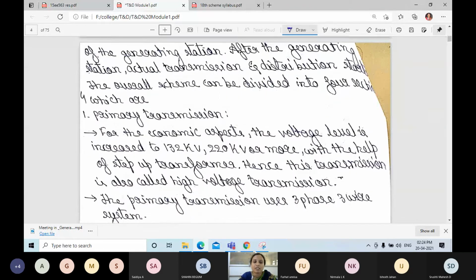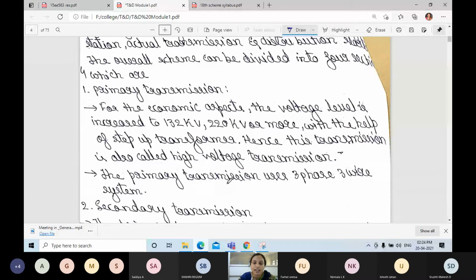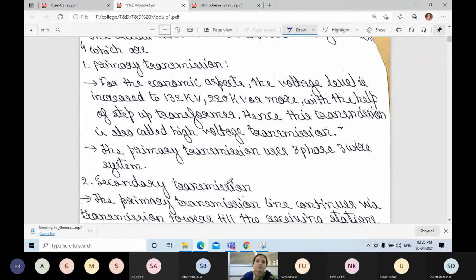First, primary transmission. For economic reasons, we cannot transmit or distribute 11 kV to the consumer because there will be losses, and finally we won't get the voltage we want. So the voltage level is increased: from 11 kV to 220 kV or 132 kV, we step up with the help of a step-up transformer. Hence the transmission is also called high voltage transmission. Here we use a three-phase, three-wire system.